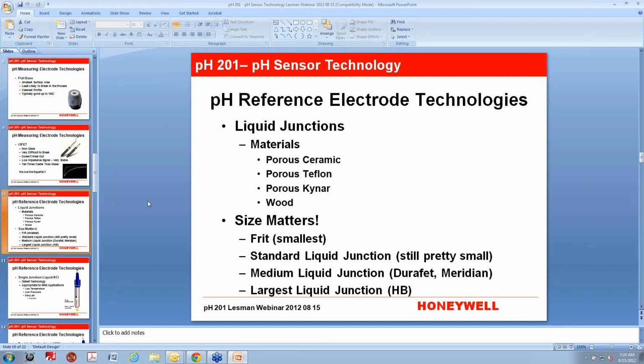The next size up would be what I would call a medium-sized liquid junction, and that would be similar to a Durafet or a Meridian. It is an annular liquid junction, which means it goes all the way around the measuring electrode, which is a much better way to do that. It gives you a little more balance and less issues with junction potentials. So that would be like a medium-sized one that is like a little annulus that goes around the measuring electrode.